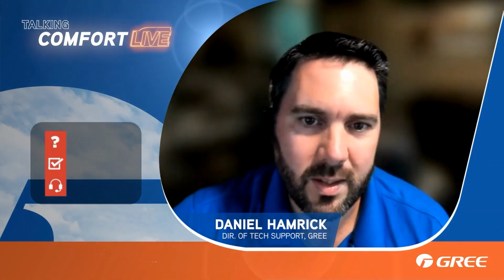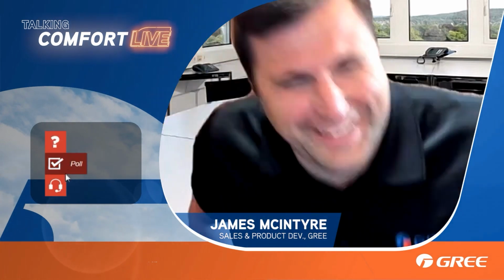Here's a pretty common question that we do get. Can you install a 2-ton flex when your load calculation is calling for 1.5 tons? Yes, you certainly can. The minimum capacity is far less than 1.5 tons on that 2-ton, but it may also give you an opportunity to use the energy saving mode that's available on the Flex to maybe provide better dehumidification, better cooling, better comfort on an application like that.